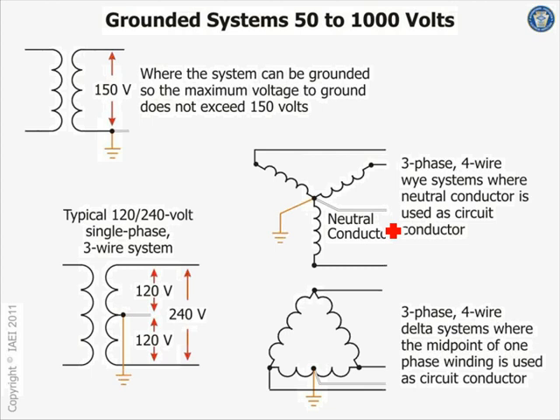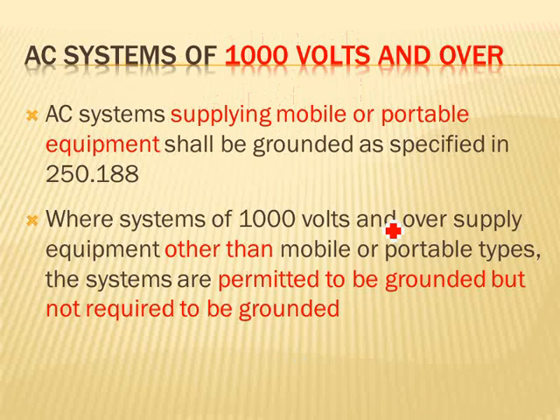If you have a three-phase 4-wire, you must ground it. If you bring a 3-phase 4-wire to a building, you must ground it. If you bring a 3-phase 4-wire center tap, same thing, you must ground it. This is 3-phase 4-wire, must ground. 3-phase 4-wire from a delta, must ground. Single-phase 3-wire, must ground. And also single-phase 2-wire, I don't know where we use that one, where the system can be grounded so the maximum voltage to ground does not exceed 150. That's when you have to ground it to limit it to 150 or less, like 120 on the secondary here coming to feed you power, and you must ground it. So these are the systems that you need to ground.